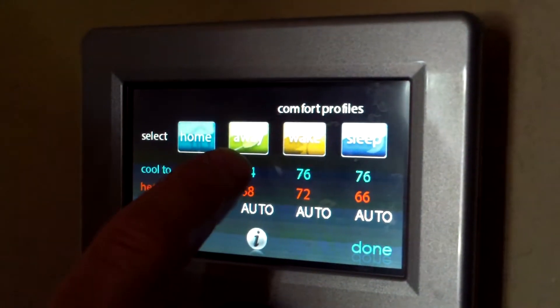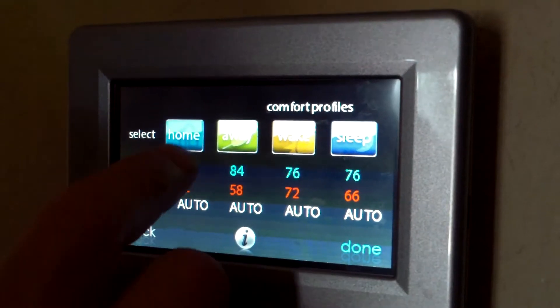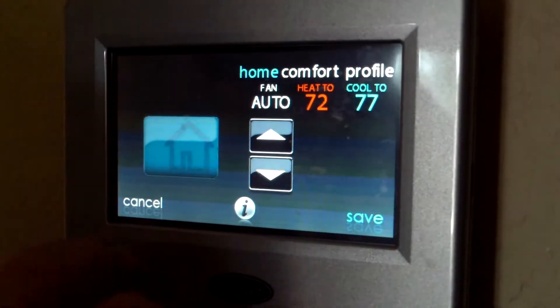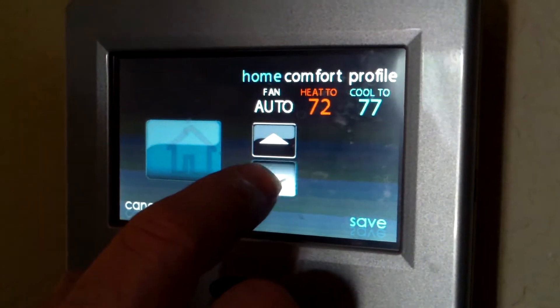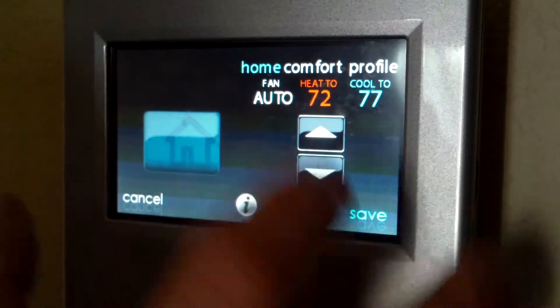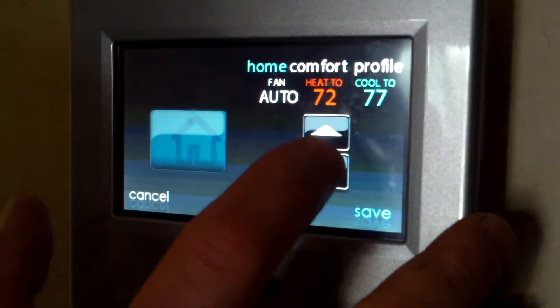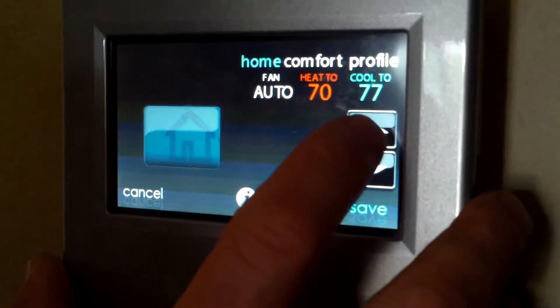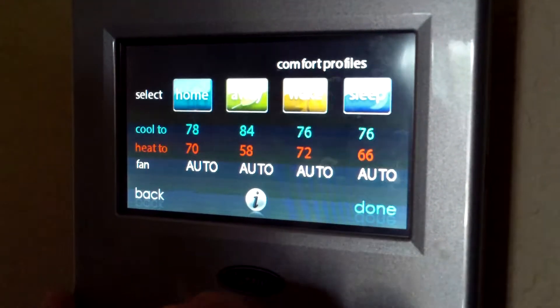At this point, you set what your temperature preferences are for when you're home, when you're away, when you're awake, and when you're asleep. You select the setting you want. Right now I'm doing my home comfort profile. I want the fan in the auto position. I want my home heating system to be at 70, and my cooling to 78, and then I save that.